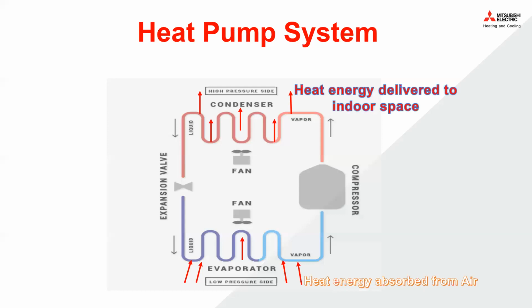So this schematic here, again, helps to illustrate the heat pump system. The compressor pressurizes the refrigerant from a low temperature, low pressure vapor to a high pressure superheated vapor. It then passes through the condenser where it condenses and gives off its heat and becomes a cool liquid. Then it goes through the expansion valve where the pressure abruptly drops, causing flash evaporation. This process absorbs the heat from the air going across the evaporator. For an example, you can think of a spray can. You hold down the spray nozzle, eventually that can will get cold. And that's the same thing. Now the refrigerant, or the substance inside, is expanding very rapidly, and then it's drawing heat, and that's what makes it feel cold.